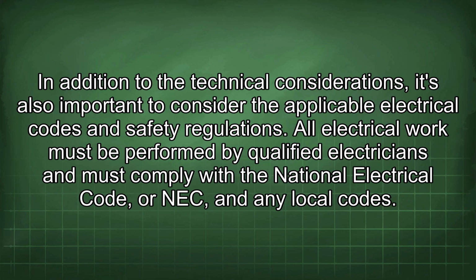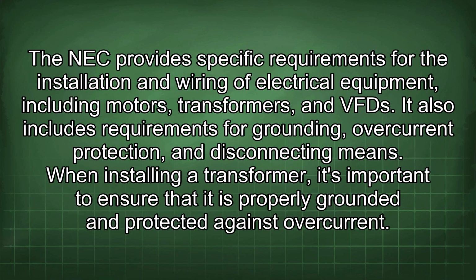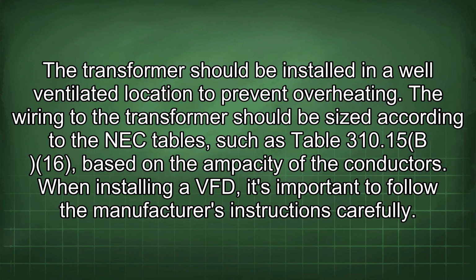All electrical work must be performed by qualified electricians and must comply with the National Electrical Code, or NEC, and any local codes. The NEC provides specific requirements for the installation and wiring of electrical equipment, including motors, transformers, and VFD. It also includes requirements for grounding, overcurrent protection, and disconnecting means. When installing a transformer, it's important to ensure that it is properly grounded and protected against overcurrent. The transformer should be installed in a well-ventilated location to prevent overheating. The wiring to the transformer should be sized according to the NEC tables, such as Table 310.15(B)(16), based on the ampacity of the conductors.